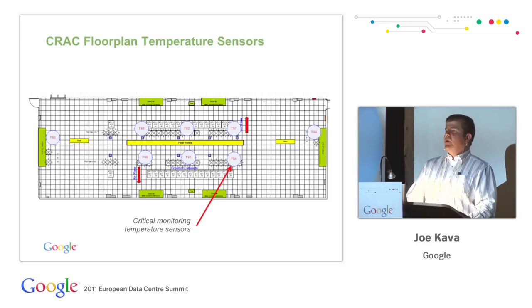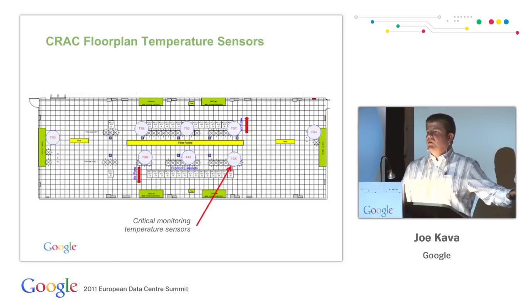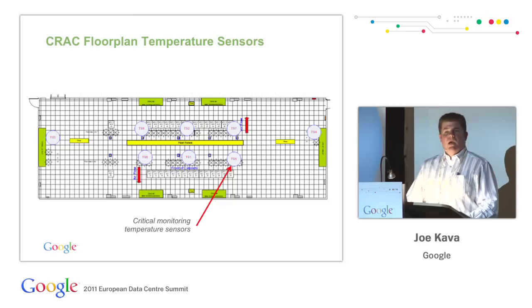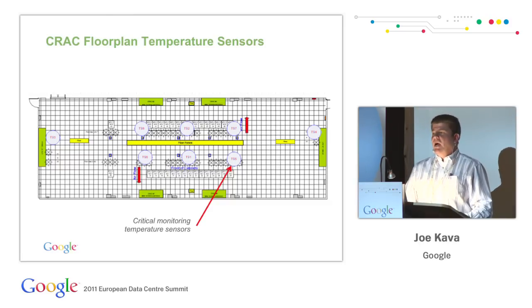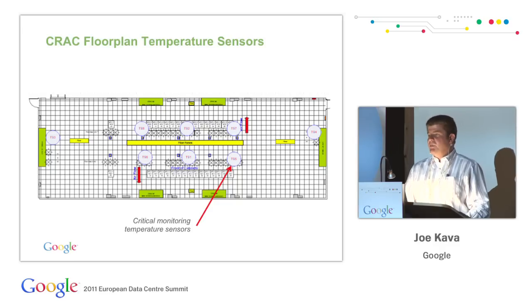I talked about establishing our critical monitoring points. On this floor plan diagram, it shows where the monitoring points were set, represented by the circles. We were monitoring in the cold aisle at an elevation of 80 centimeters above the raised floor. We were monitoring in front of the higher density cabinets and the lower density cabinets, and most importantly in front of the UPS battery cabinets as well. We use this data to establish that we were maintaining our cold aisle temperatures properly, and this ultimately became the feedback loop for an improved control algorithm for the CRACs that I'll talk about next.